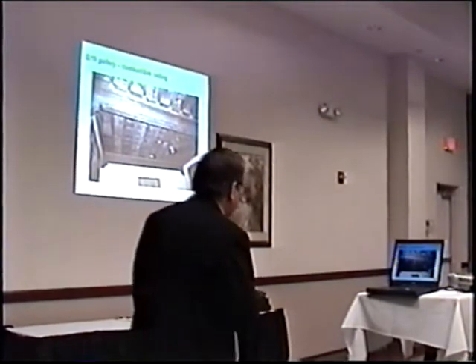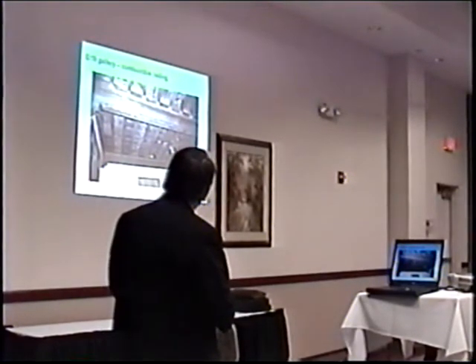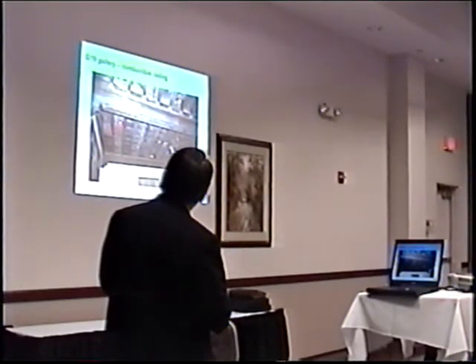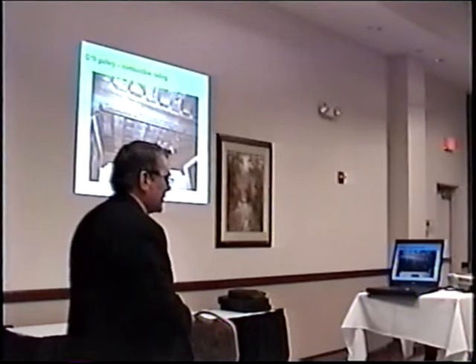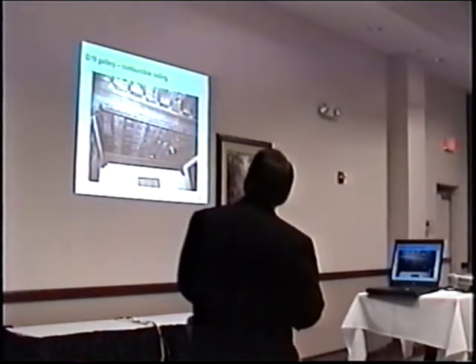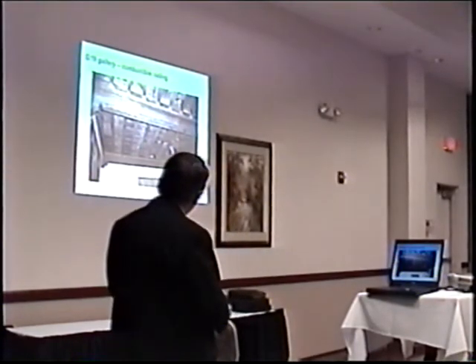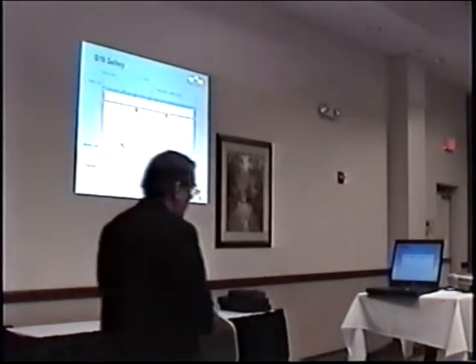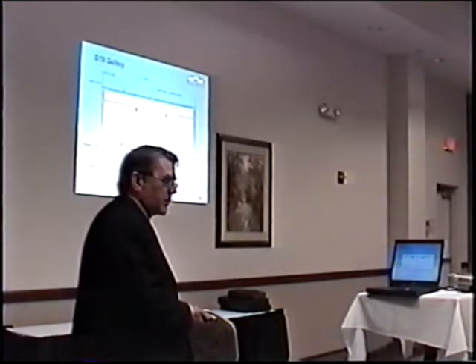The other gallery is the G19 gallery, which had a beautiful ceiling from, again, I think it was an Italian vintage area. This is the driest tinder wood you could ever imagine. Get up above that. That wood is just like light cedar, like balsa wood, and extremely dry. There's electric wiring laying up above there, and that ceiling is what is combustible. There's marble walls and there's some tapestries on the walls, and that's about it. So the objective, starting with the G19 gallery, was to protect the combustible ceiling in an otherwise marble space with almost no other combustibles.